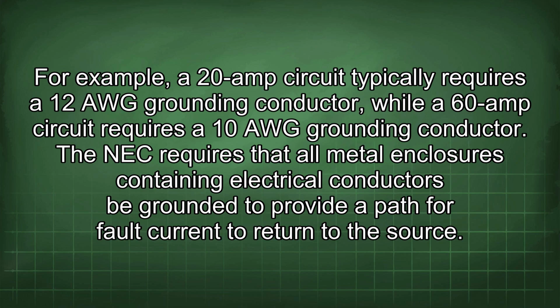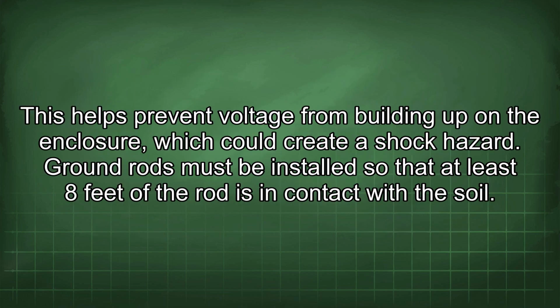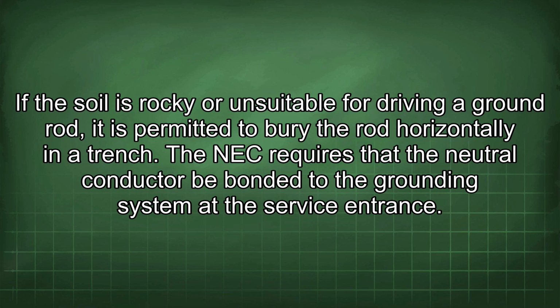The NEC requires that all metal enclosures containing electrical conductors be grounded to provide a path for fault current to return to the source. This helps prevent voltage from building up on the enclosure, which could create a shock hazard. Ground rods must be installed so that at least 8 feet of the rod is in contact with the soil. If the soil is rocky or unsuitable for driving a ground rod, it is permitted to bury the rod horizontally in a trench. The NEC requires that the neutral conductor be bonded to the grounding system at the service entrance.